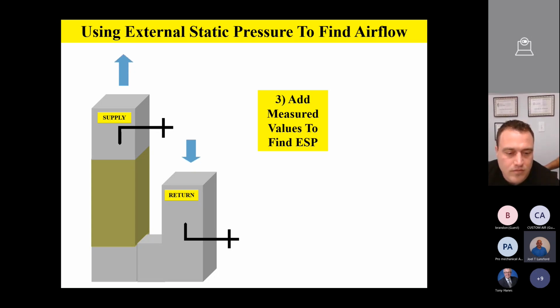So just remember, this is the easiest way to remember it. You always want to read the maximum suck on the fan, whatever is going to provide the maximum suck. So if I've got a filter right here, look at my cursor, I'm going to take that static pressure probe and put it on the back side of the filter. If I've got a return air filter up here, maybe where this arrow's pointing on the return, and I've got a filter up in the ductwork somewhere, I'm going to put it right where it is right now. Because we always want to read the maximum suck against the fan on the return side.